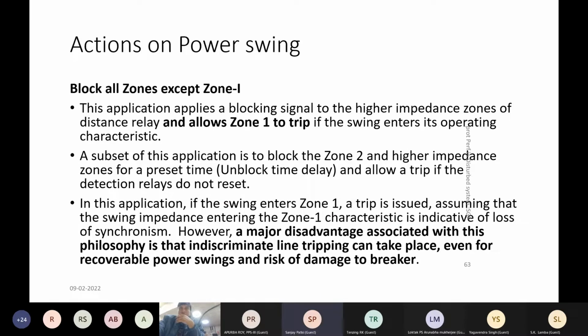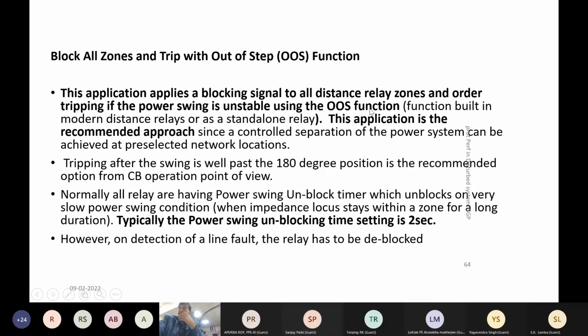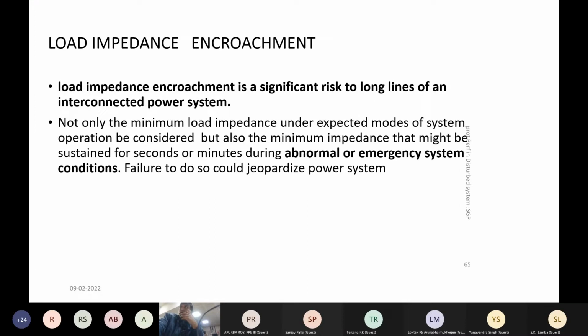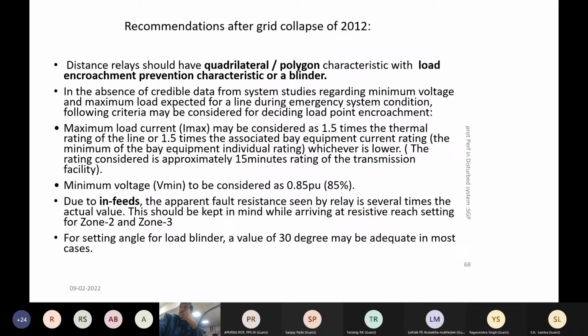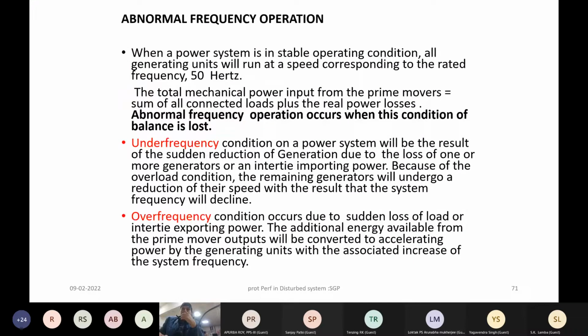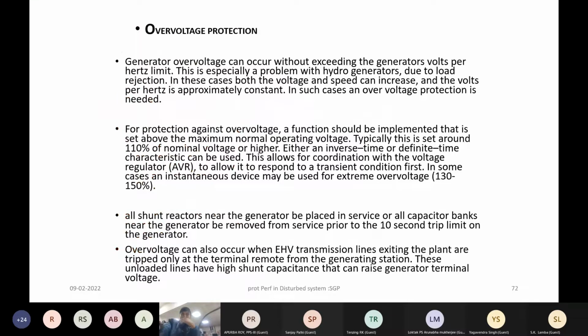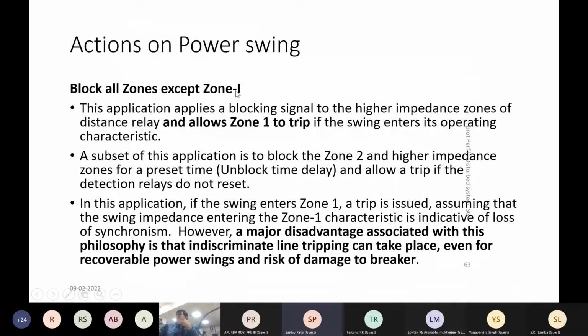Now, if you see the power swing seen by the transmission line, one of the practices which is prevailing is we block zone 2 and zone 3 except zone 1. This is the philosophy which perhaps is still existing at some of the stations.